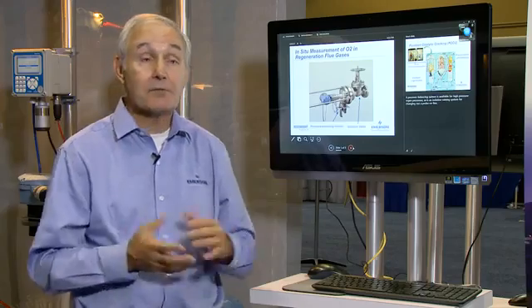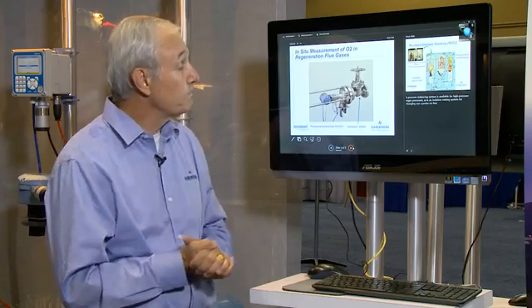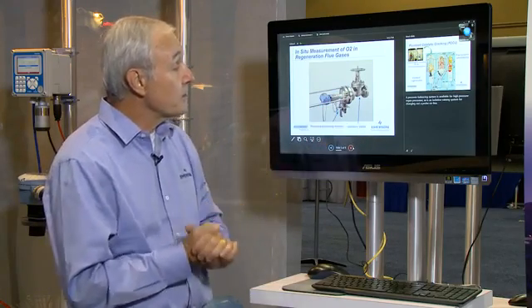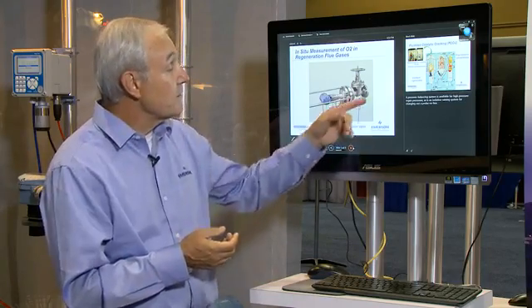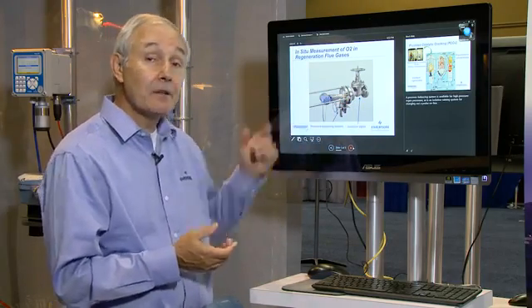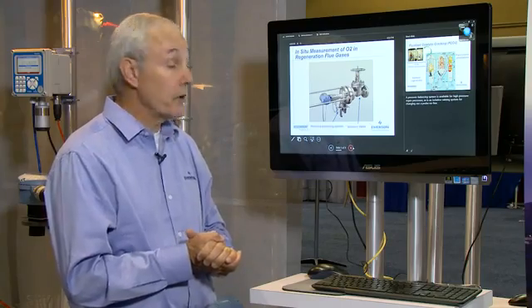Temperatures can be as high as around 900 degrees Fahrenheit. So this is an isolation valving system and also a pressure balancing system that compensates for the pressure. The isolation valve permits you to get the probe in and out while the unit's operating.